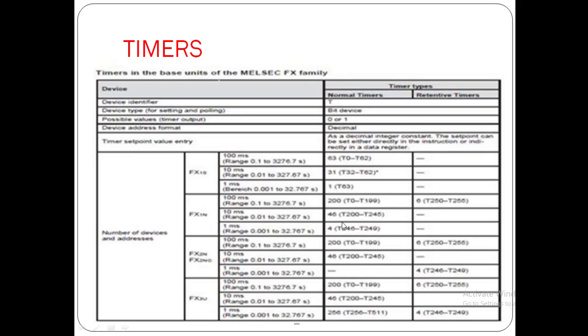In FX1N, 100ms timers consist of 200 normal timers and there is no retentive timer in that sub-range. In FX2N, there are 200 normal timers and 6 retentive timers. In FX3U, 100ms timers are 200, T0 to T199, and 6 timers are retentive timers T250 to T255. You can also have 10ms timers which are 46, available from T200 to T245. There is no 100ms retentive timer in FX3U.